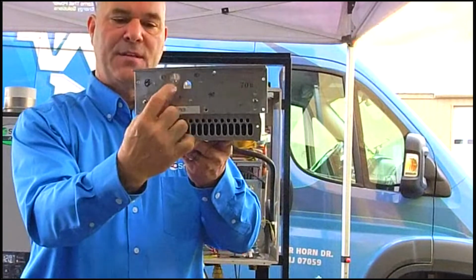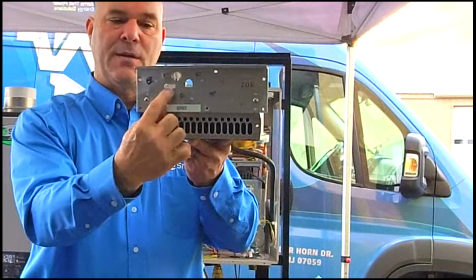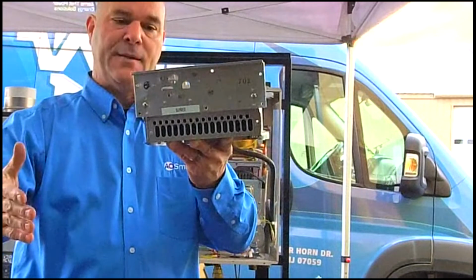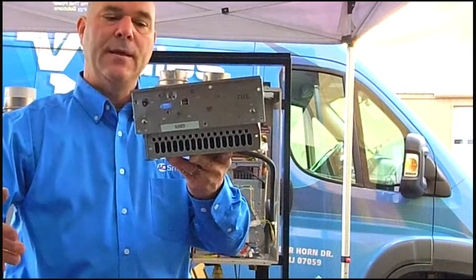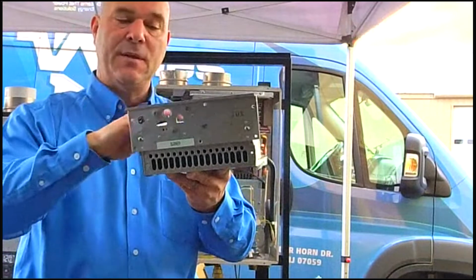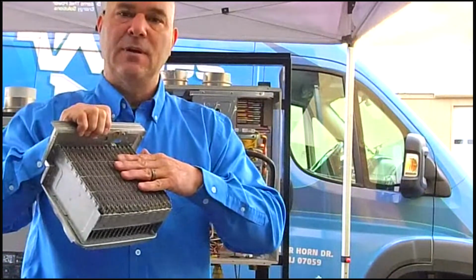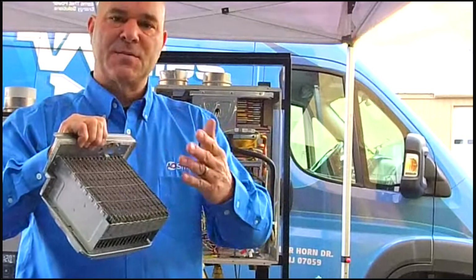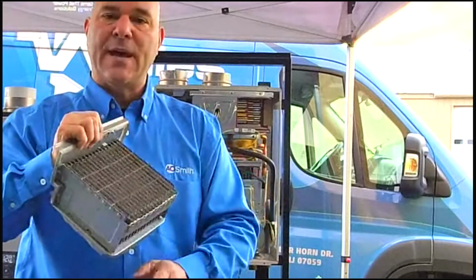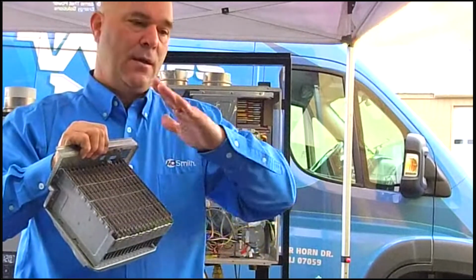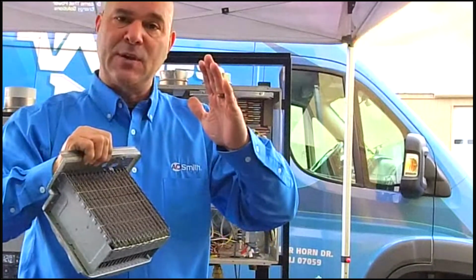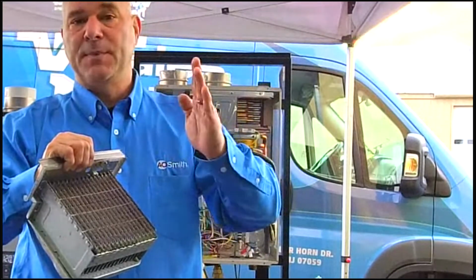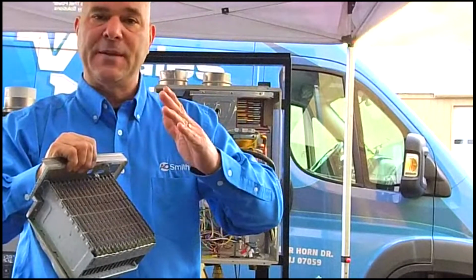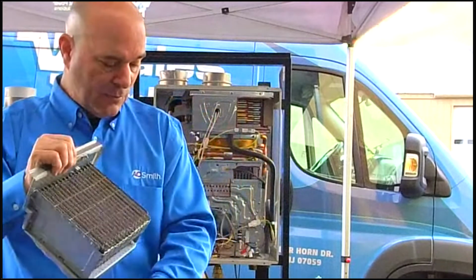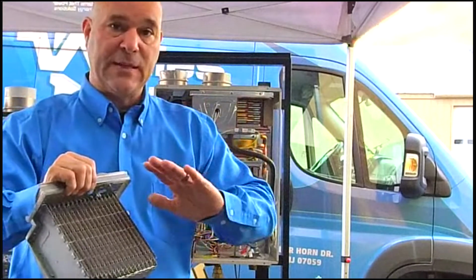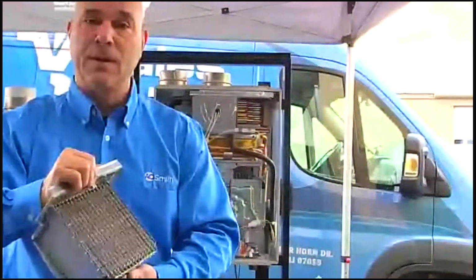There's a sight glass here. You can see the flame. And then over here will be what we call a flame rod and an air fuel ratio rod. What that air fuel ratio rod does is monitor the temperature of the flame, and it will make adjustments on the fly. So if we don't have perfect combustion, it will either open up the proportional valve a little bit if it needs more gas, or it will speed up or reduce the blower motor depending on what's going on for combustion. You don't have to do anything. You don't have to set that up. That's built into the unit. It's going to do it on its own.